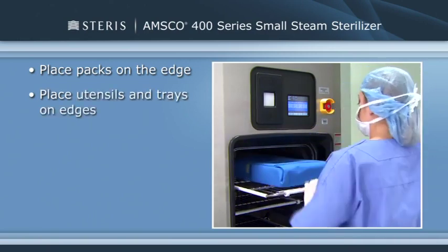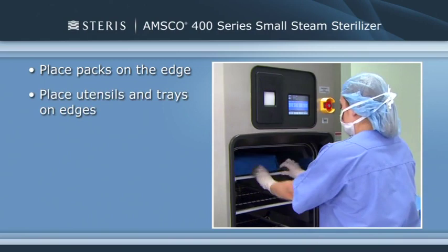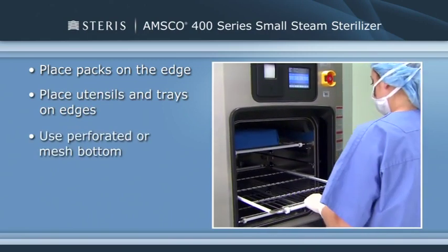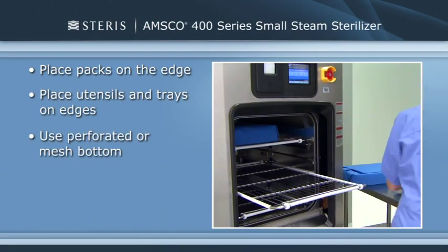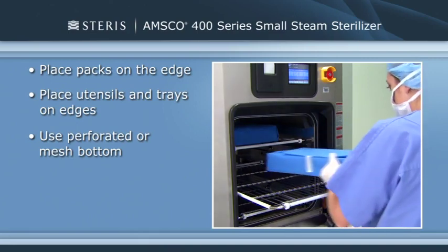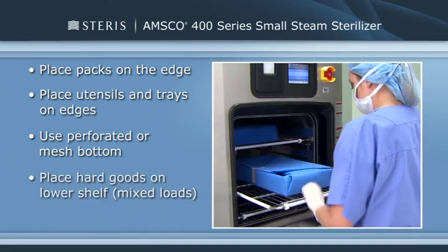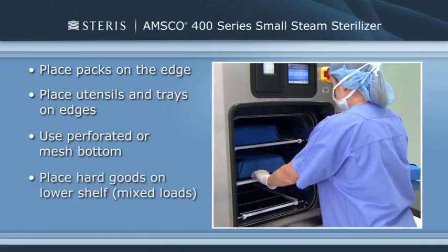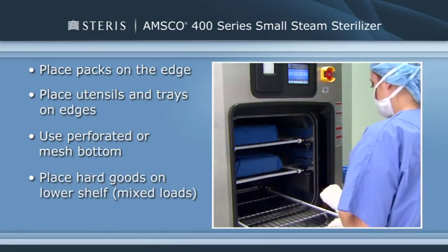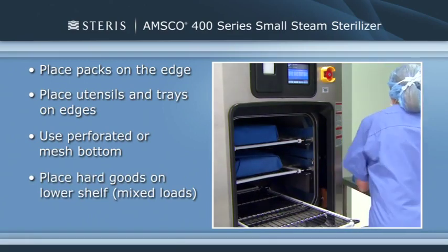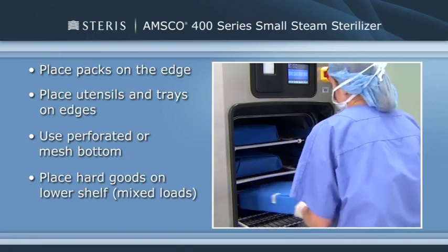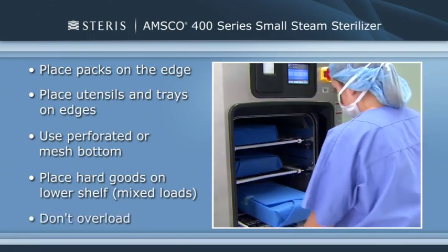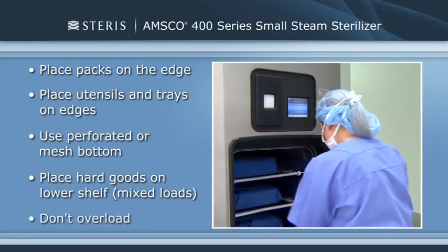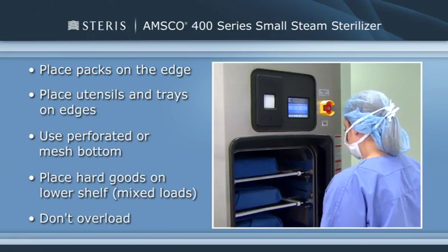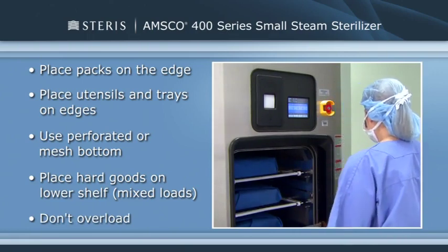Place utensils and treatment trays on their edges so they will be sterilized and properly dried. Place instrument sets in trays that have a perforated or mesh bottom. Place flat. If mixed loads of fabrics and hard goods, place the hard goods on the lower shelf. This reduces the wetting of fabric packs from condensate dripping from a hard goods load. Be careful not to overload the sterilizer. Allow for steam penetration between packs. Avoid contact with the wall of the chamber.